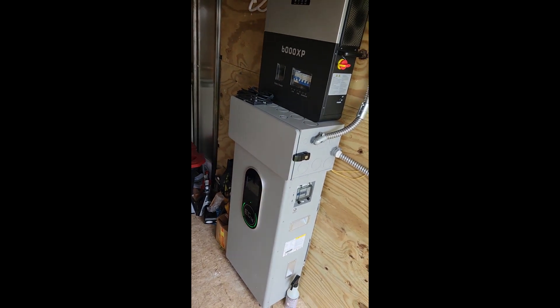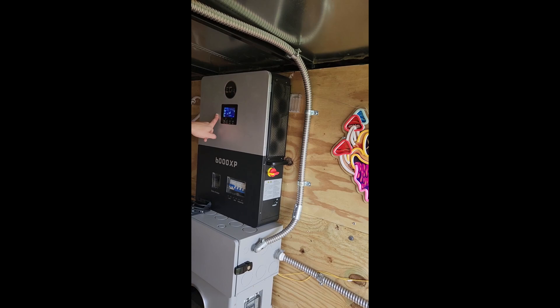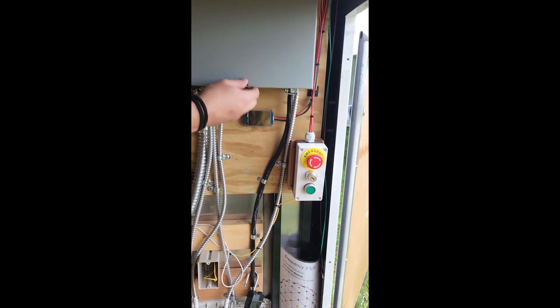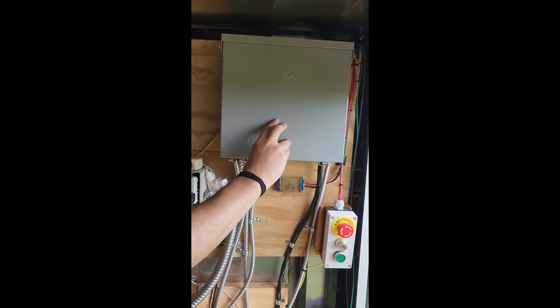Batteries are DC as well. Right now the people collectively are using about 2,000 watts of power, which is basically a third of what this system can put out. And it's running to this panel, which goes to our 50 amp breaker and then four 20 amp circuits. That's a lot of juice.